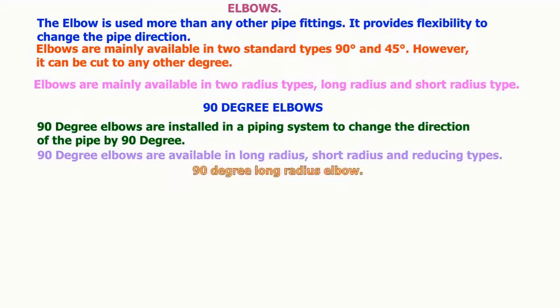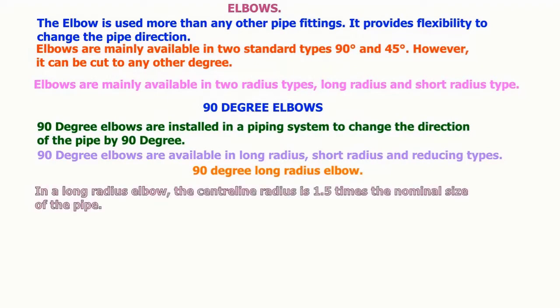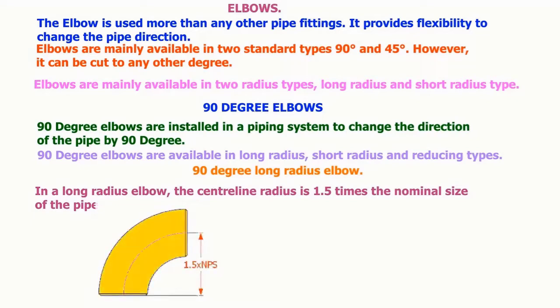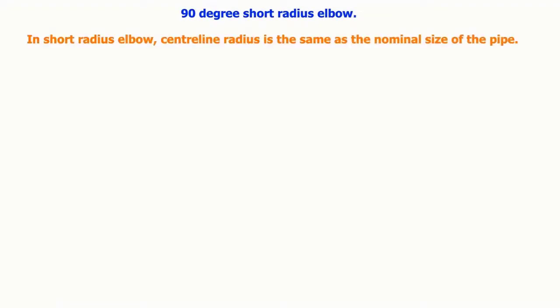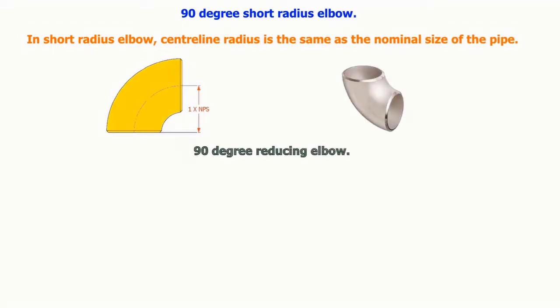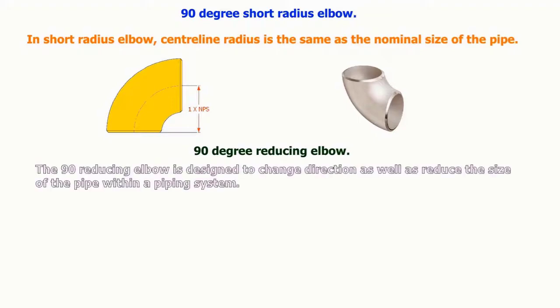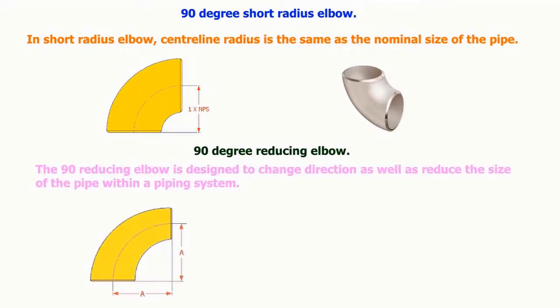In a long radius elbow, the centerline radius is 1.5 times the nominal size of the pipe. In short radius elbow, centerline radius is the same as the nominal size of the pipe. The 90 reducing elbow is designed to change direction as well as reduce the size of the pipe within a piping system.